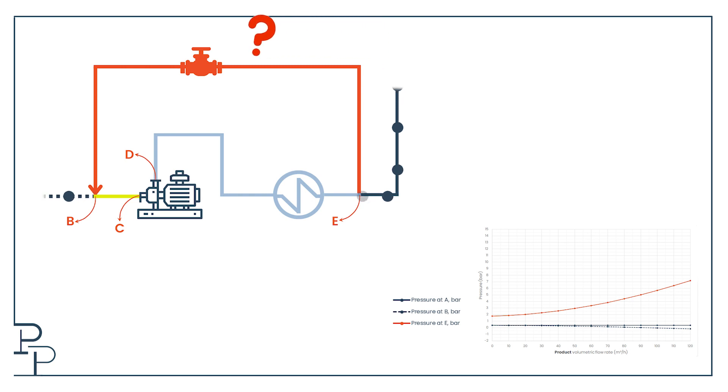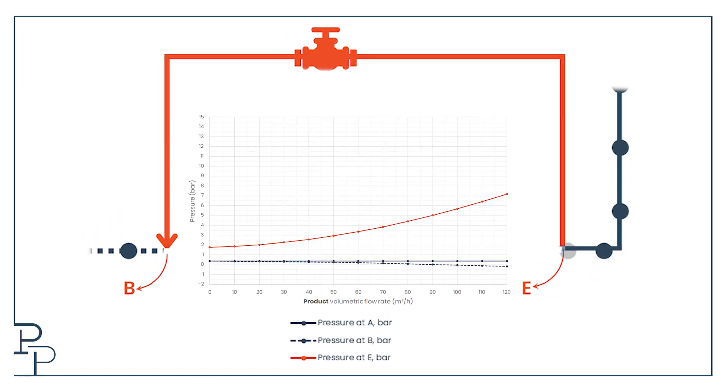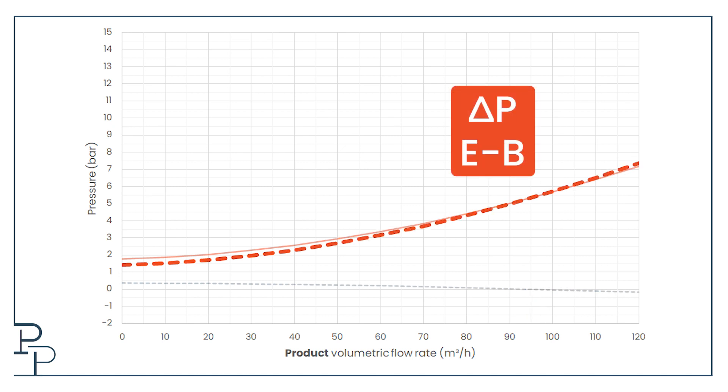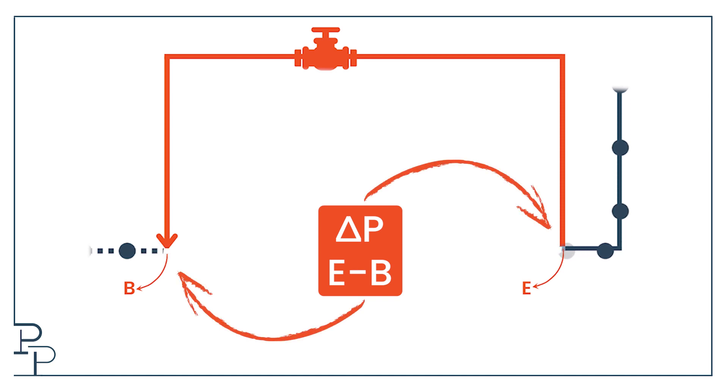But now look at what's happened. I may not know what the recycle flow rate is, but I have a curve describing the pressure at B and I have another curve describing the pressure at E. That means I know the pressure drop between E and B by subtracting one from the other. But understand, this isn't the system curve for EB because I'm not plotting it against the recycle flow. I'm plotting it against the product flow. I am plotting the pressure drop in the recycle line as a function of a flow that doesn't even go into the recycle line. However, that other flow does dictate the pressures on either side of the recycle.